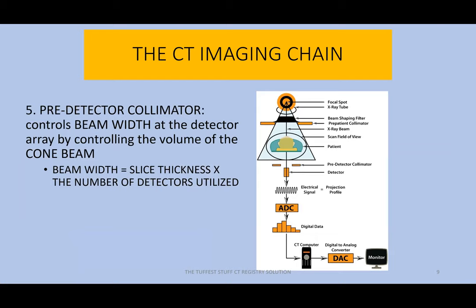Component number five is the pre-detector collimator. The pre-detector collimator is responsible for controlling the beam width at the detector array by controlling the volume of the cone beam.